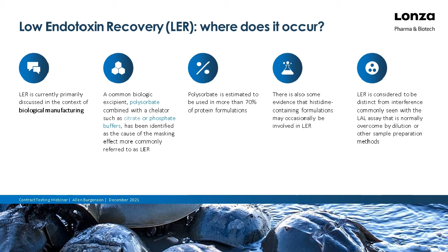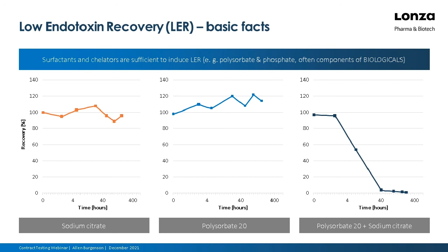So with LER, remember, it's a two-part issue. If you just have sodium citrate in a sample and you do your spike, over time the spike remains fairly stable, and that's seen in orange here. If you just have polysorbate 20 and you spike, over time you'll see it should be fairly stable or slightly rise. That's because of the dispersion characteristics of the surfactant, but it should stay fairly stable. However, if you have both polysorbate and sodium citrate in your solution, you'll spike, and then over time the apparent endotoxin levels appear to fall. And I should say that is apparent endotoxin, because the endotoxin is still there. It's just bound up inside of a micelle.